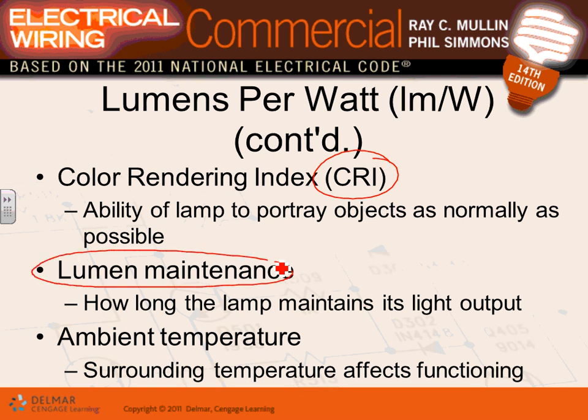Lumen maintenance — also called lumen depreciation factor — is how long the lamp maintains its lumens. If a fixture is rated at 3000 lumens, how long will it maintain those 3000 lumens? Will it stay at 3000 for 24,000 hours or will it dip before that? The longer the lumen maintenance, the better the output over time.